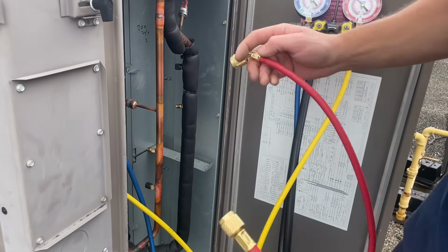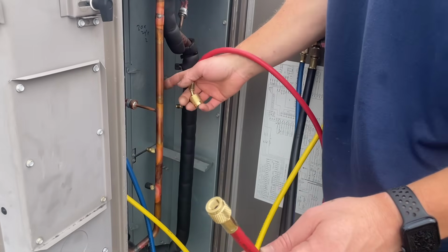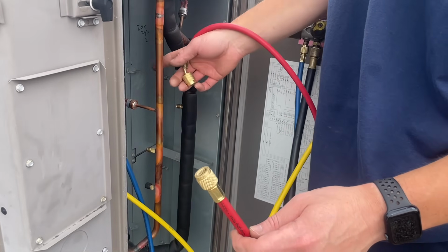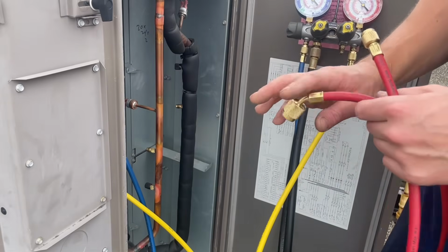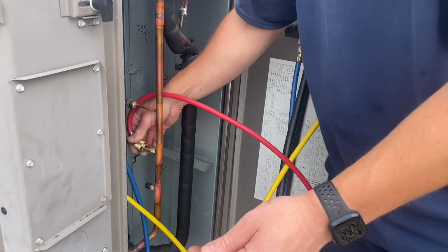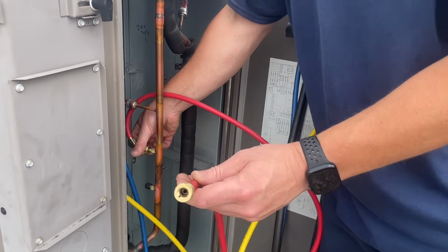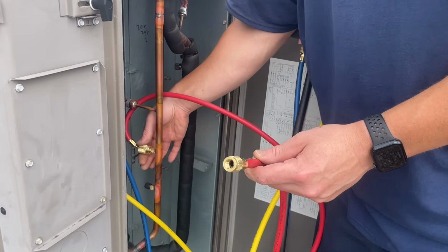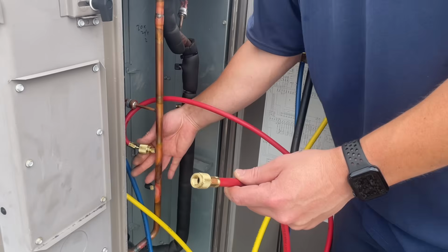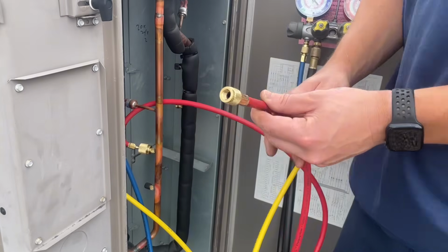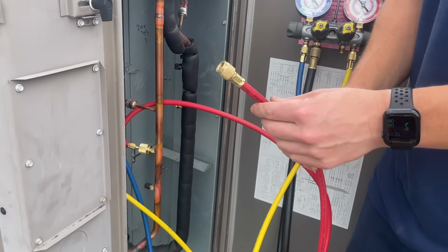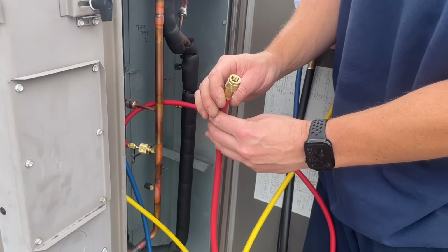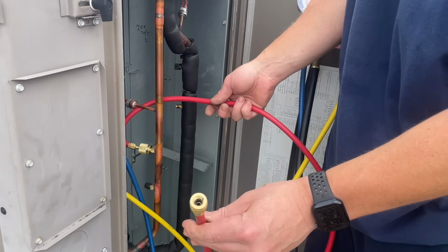So check this out. This is our discharge line off compressor 1. We're not hooked up there right now. We're on compressor number 2. But if I was to thread this on here open, this would all shoot into the ambient. Watch. Fully tightened. Nothing. We're not registering any pressure through this hose. I have never seen brand new hoses do that before.